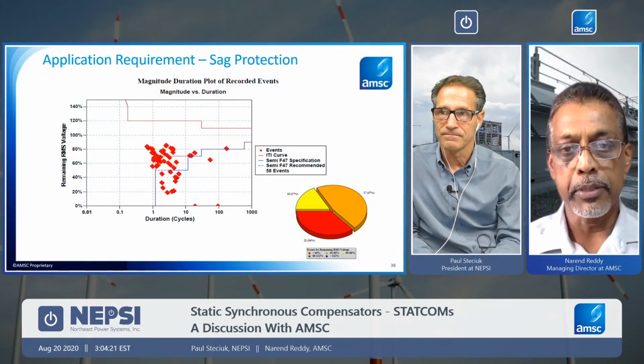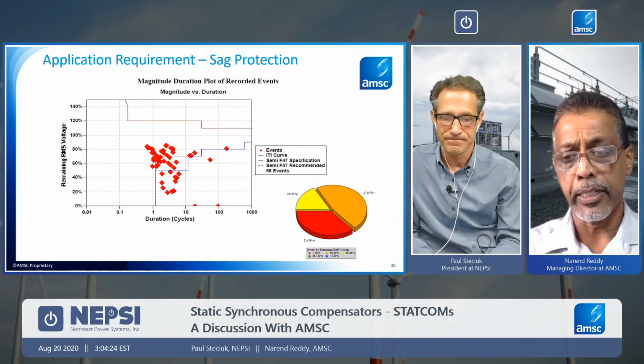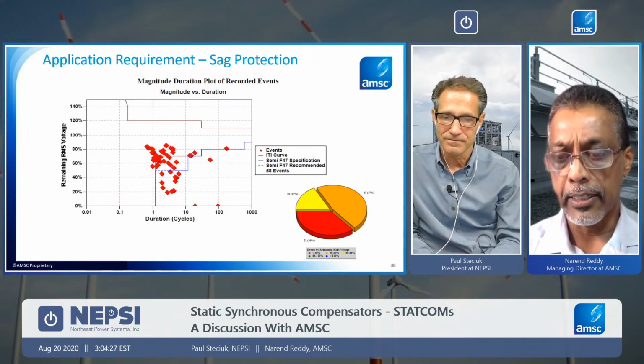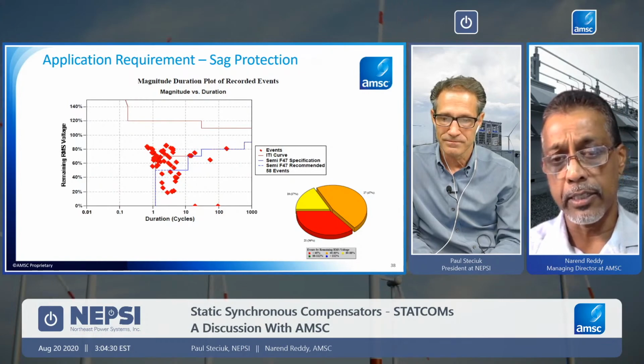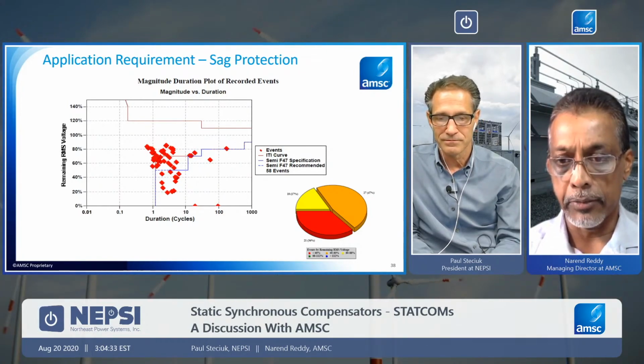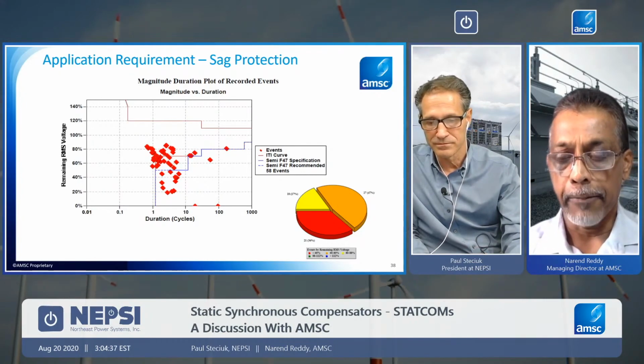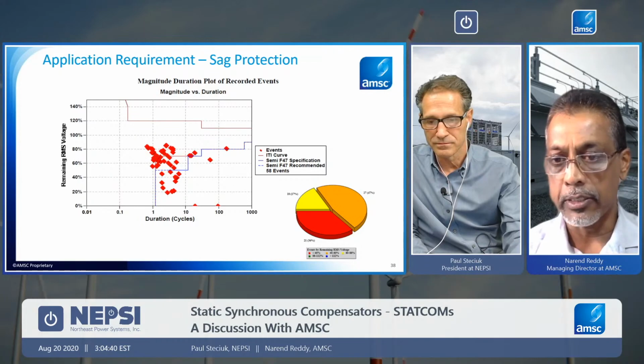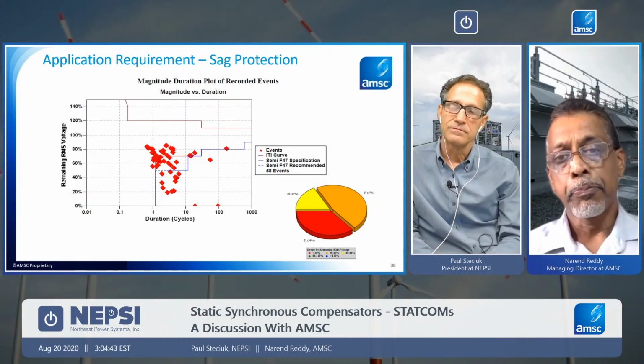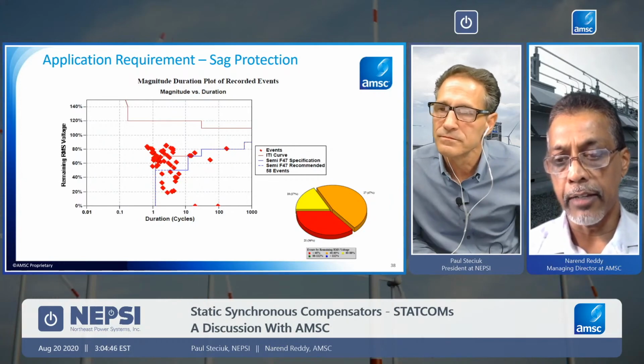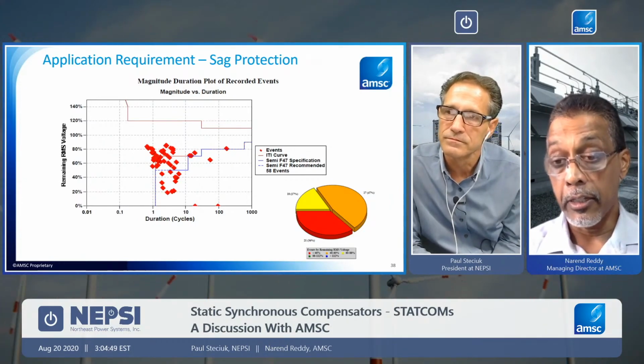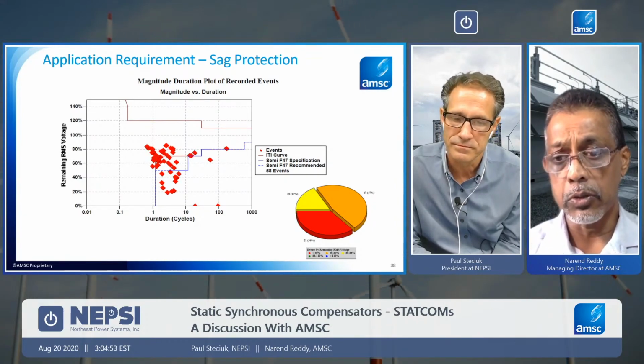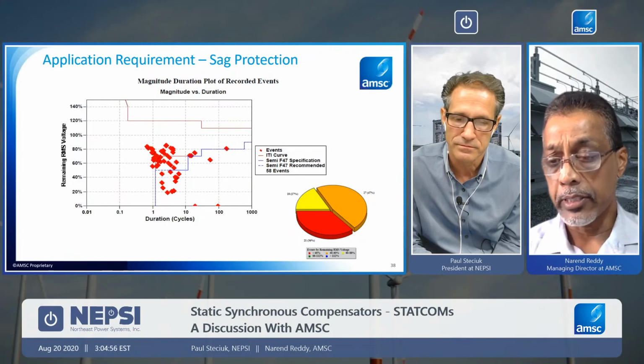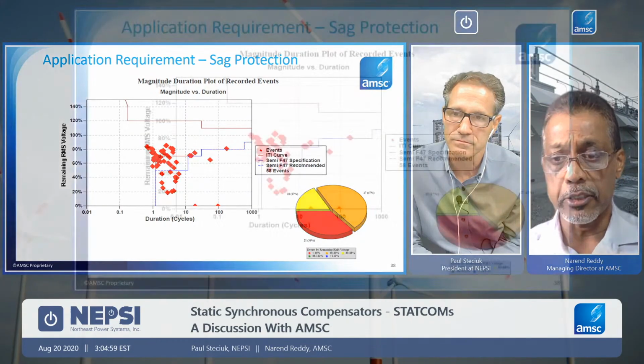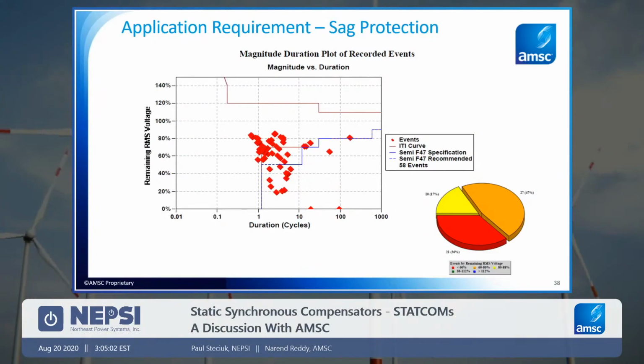Sure. So in the sag protection realm, as you mentioned, this is protecting a critical facility, or a process of the critical facility, from external sags, and we're talking about sags that are happening out on the grid, through lightning or just faults in the system, single phase, two phase, or three phase. But the facility itself has some critical processes, equipment, tools that may be very, very sensitive to momentary sags, and those sags or disturbances that happen out on the transmission system permeate right into the facility.